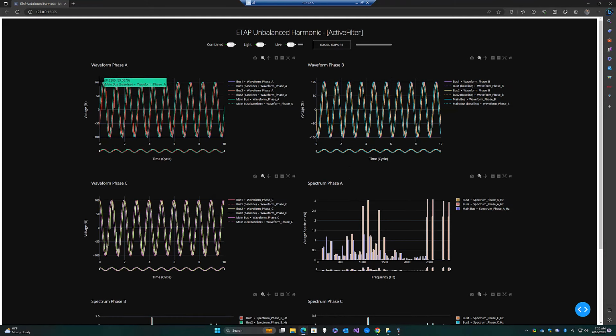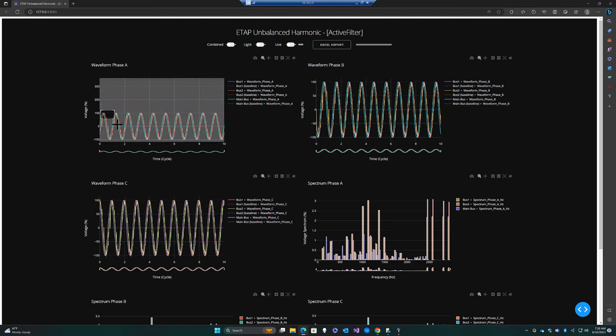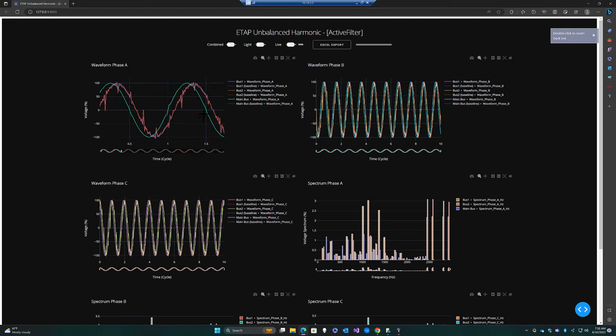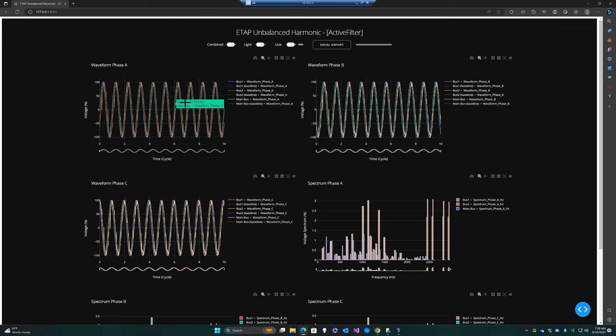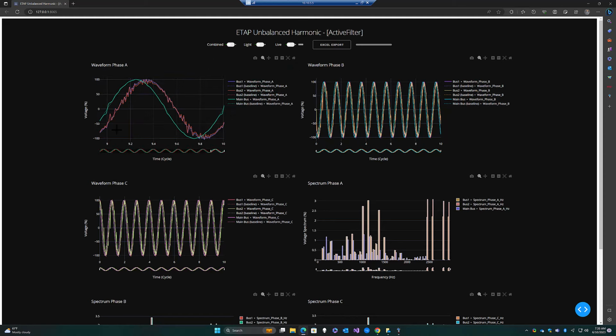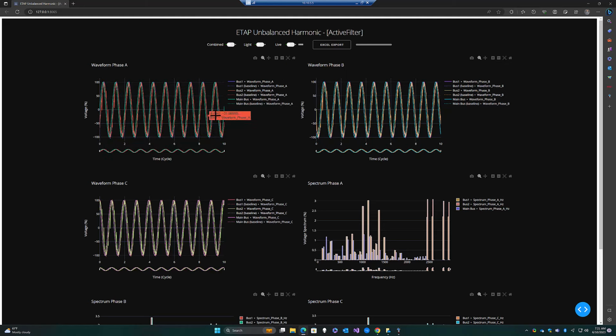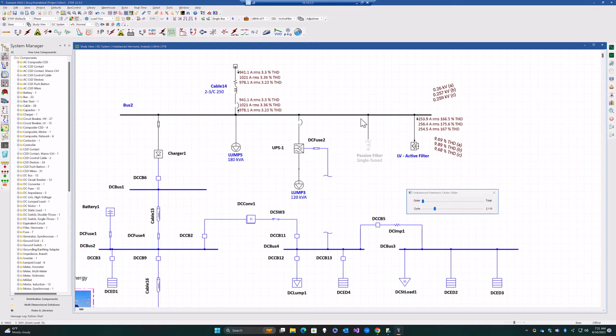So we can see in our analyses, we can see a significant amount of distortion that ultimately we can reset, and we can look at the resulting waveform, and we can see some of those spikes have been eliminated. So that's essentially the active filter working as a function of time, measuring, compensating, and then finally correcting the distortion on each particular phase. So again, there's a lot more detail behind what I'm explaining here, but hopefully gives you an indication of how the active filter works with the unbalanced fundamental modes as well as the unbalanced harmonic modes, which is new in ETAP 2023.